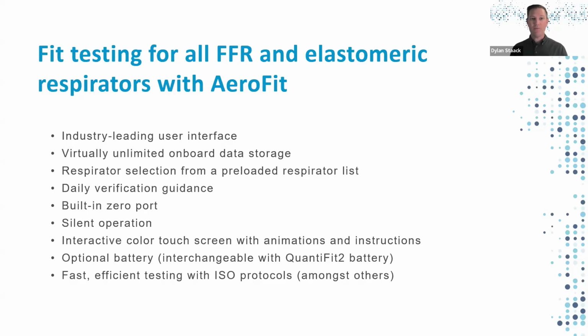I just said connect the tube to the correct port. So one of the other things that we included is a built-in zero port. Anybody that has been conducting CNC fit testing has had to carry around small plastic zero filters. They're super effective and they work well, but the issue with them is they crack or they get lost. And then you get on site or you go to execute a day of fit testing and you can't do a daily verification because you don't have a zero filter and you have to order one. We have taken that away from your hand and put it inside the unit. So that zero filter is built into the unit, and all you have to do is attach the clear line to the built-in zero filter to be able to get a zero check on your instrument.